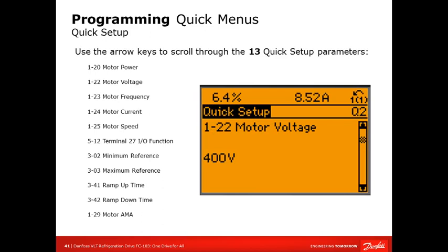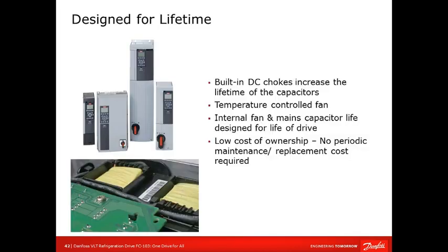Motor AMA: one thing Danfoss can do is we don't have to spin the motor, but we can run an automated motor adaptation. Basically the drive, being wired to the motor, can enhance the performance of the drive, and it can send some pulses of current just to get a sense of the rotor and stator. It only takes a couple of minutes, but it's something we recommend. It just fine tunes the VFD with the specific motor, so it's an option. Again, it's not difficult to do.